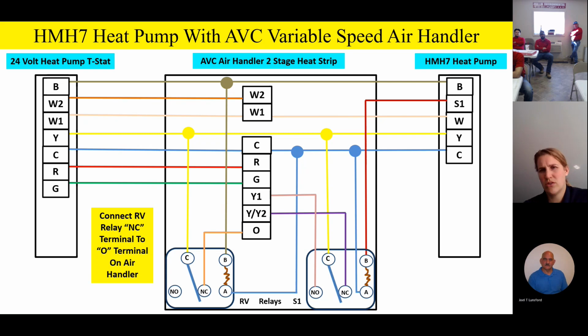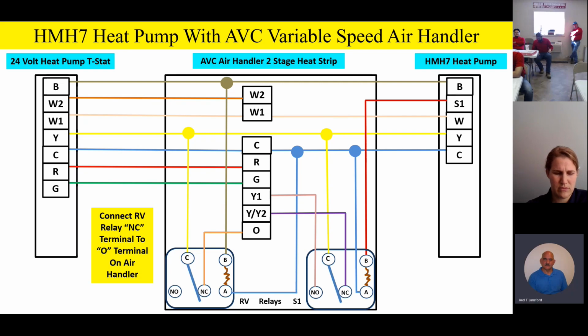So that's why they energize it in cooling mode instead of in... Is that why they have it configured the way that they have it, outside also, so that you have to energize orange to get cooling normally? So you have to energize orange on the indoor product to get the cooling blower functions inside. Outside, with the outdoor unit, if there is no O outside, there's a B terminal for heating. So if the outdoor unit doesn't see a B signal for the reversing valve, it defaults to cooling mode.